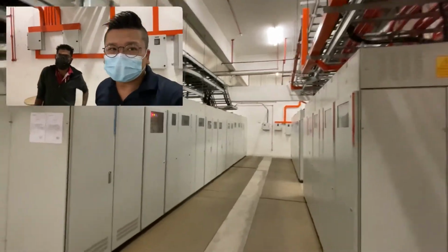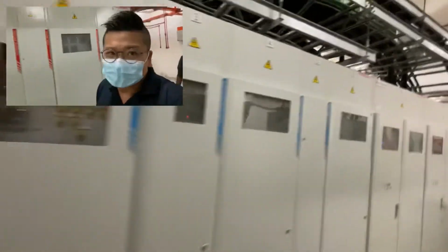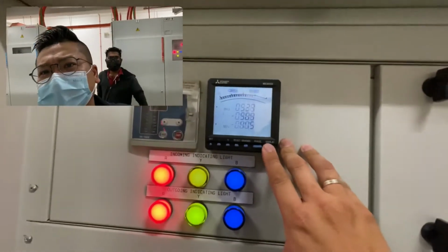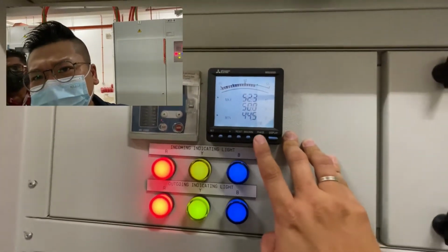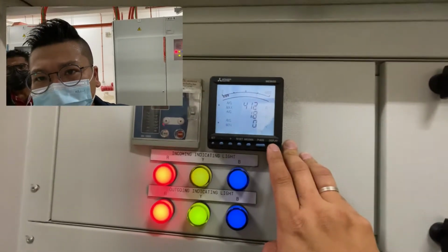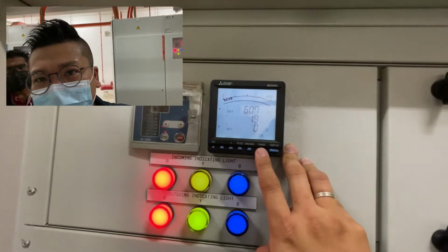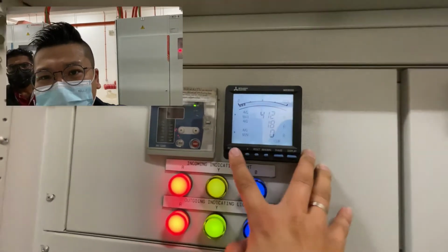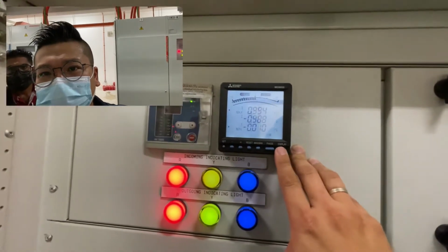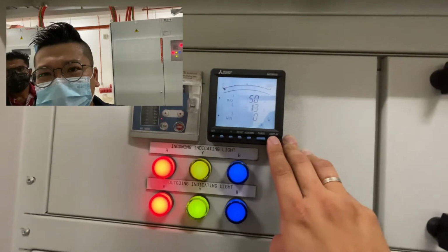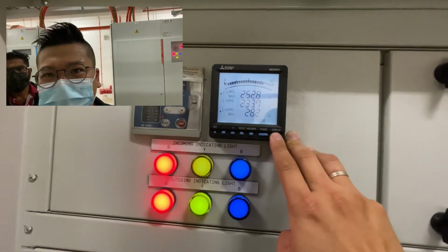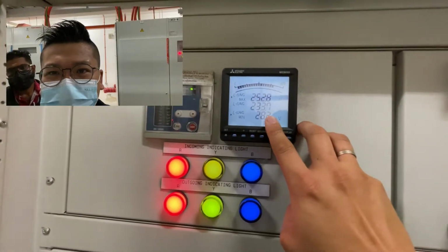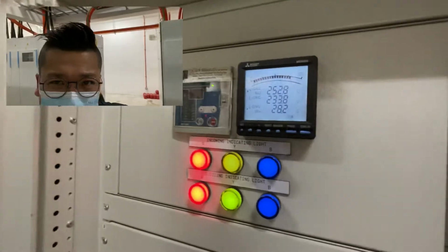Okay, this is the LV room. Currently, now we are at the LV room. Let us check the voltage for transformer 1. This is MSB 1. Okay, frequency. Maximum 600 amp. So it's normal, no? Yeah, it's normal. It's quite low. No usage. Average low side is 233, high side is 252, still below 253 volt on the single phase, so shouldn't be any problem.